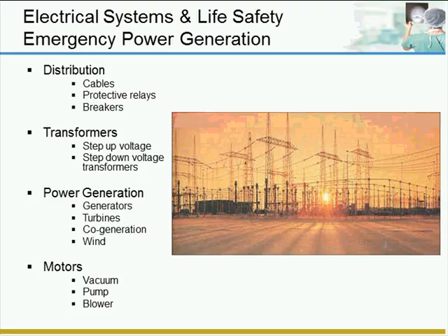Safety and emergency power can be provided by a number of different sources. We just talked about the most common, diesel generator. That was in the prior picture. You could also have a steam turbine, which operates in conjunction with the steam boilers. And in some cases, you might also have a gas turbine feeding a steam turbine, which then feeds a generator.